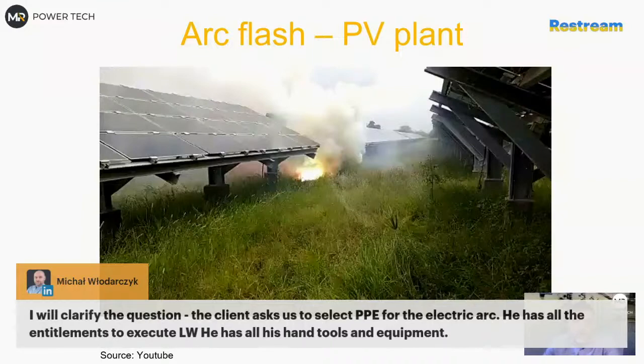what is the energy. And the only thing they can do, they can follow so-called table method from CSA Z462 or from NFPA 70E, where the table method is just simple try to estimate energy based on previously done calculations by IEEE committee. When they would tell you, okay, this is a low voltage switchgear, we have a distance, we have a voltage up to 600 volts, we have energy, we expect short circuit current to be 50 kiloamps, and the breaker should trip in 100 milliseconds. And then you assume, yes, we have PPE category 2, maybe PPE category 4. I can tell you this thing goes very fast to PPE category 4.